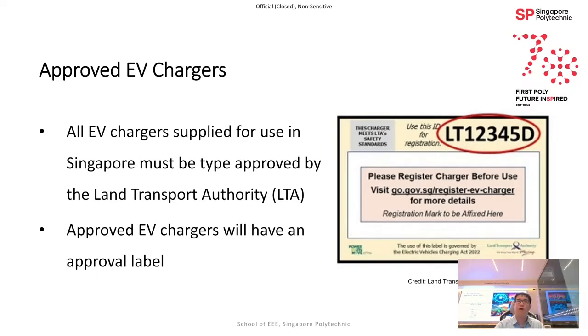In order for an EV charger to be allowed to be sold in Singapore, it must first be type approved by the Land Transport Authority. Before LTA approves this model, it will require either the manufacturer or the importing agent to show that the EV charger model is able to meet this criteria by actually sending them to an approved laboratory for testing and obtaining a certificate.